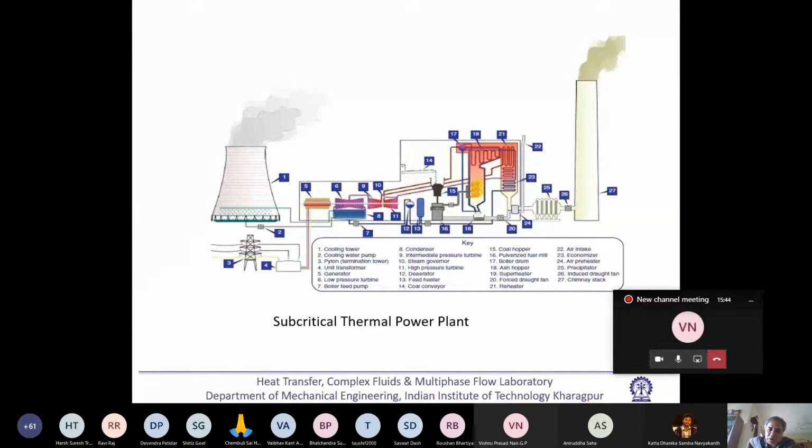And also, it is not done that way because just from the pond or river, we cannot take water and put it in the condenser, because that water will have a lot of impurities. So water is generally treated. Otherwise, in the condenser, there will be a lot of corrosion problem and fouling. This is a heat exchanger. So this is called the fouling problem.